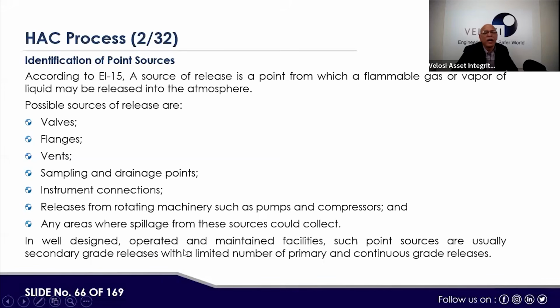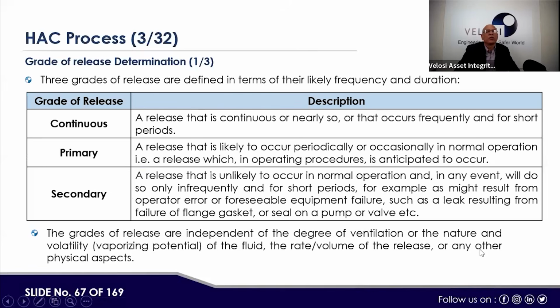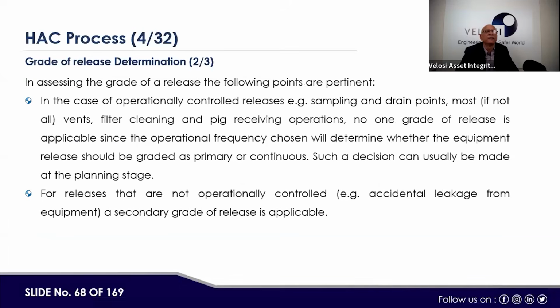So in well-designed, operated and maintained facilities, such point sources are usually secondary grade release with a limited number of primary and continuous grade releases. We have already covered this: continuous means inside the vessel, then primary, and then secondary, where continuous is always available, primary is sometimes available, and secondary is random, rarely available. Hydrocarbon could be ignited by an ignition source, and we need to control the ignition source accordingly.